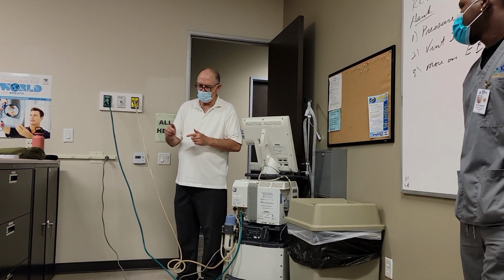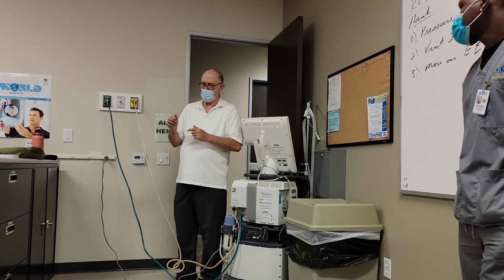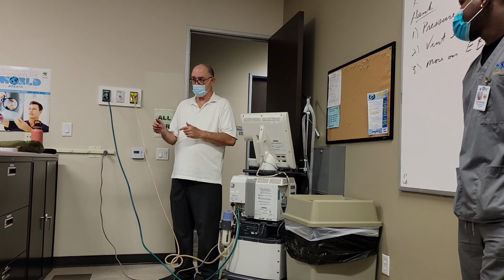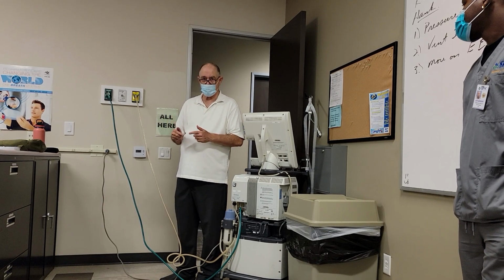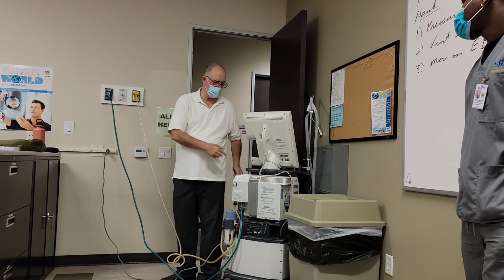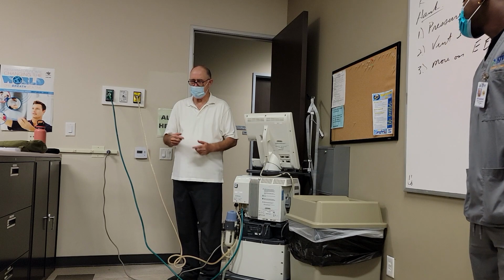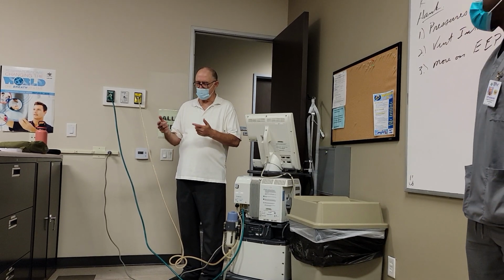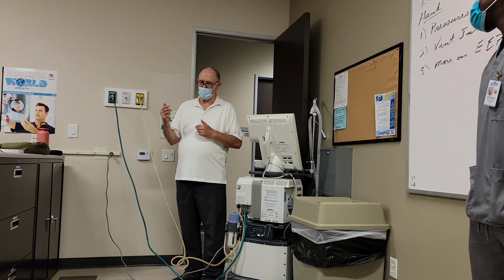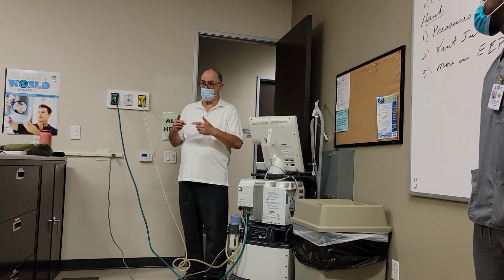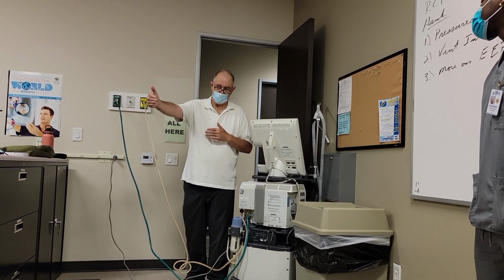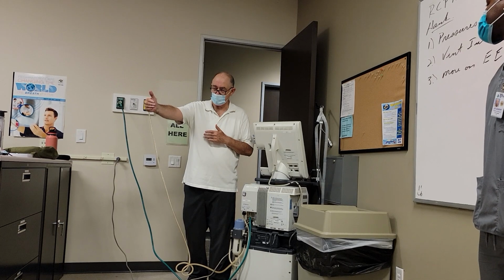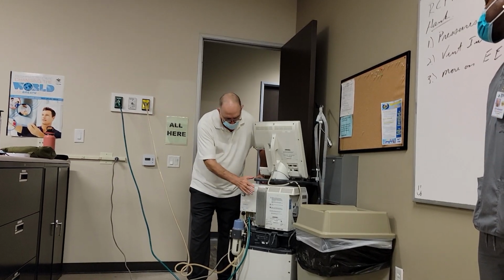Just the other side of the proportional solenoid valve is a series of sensors. The first sensor is a pressure sensor, looking at the airway pressure coming out. Okay? There may be a flow device there also, and the flow and the pressure will tell you pressure volume coming out of the ventilator. Okay?